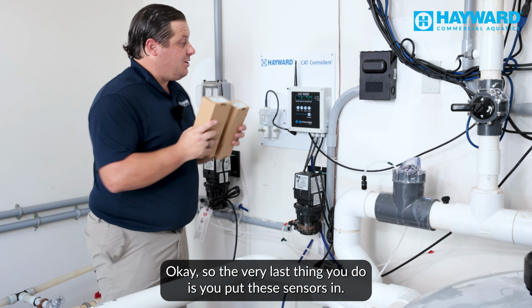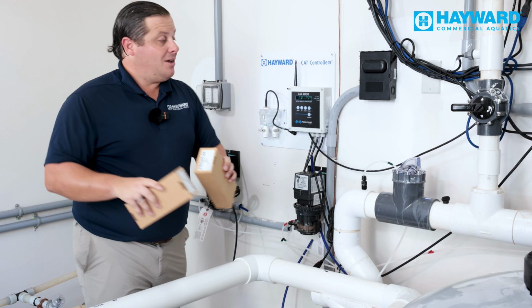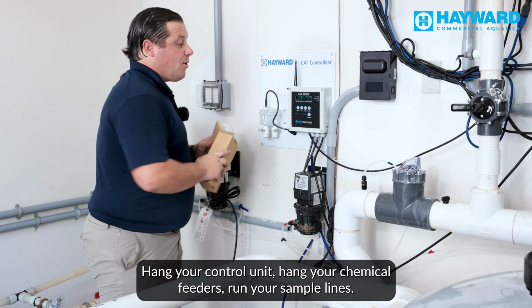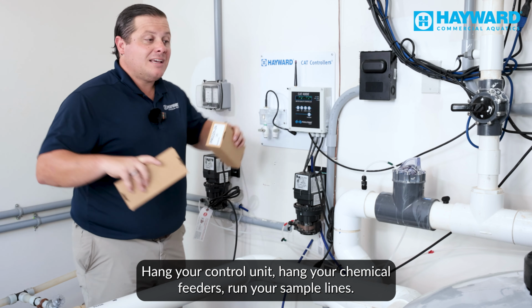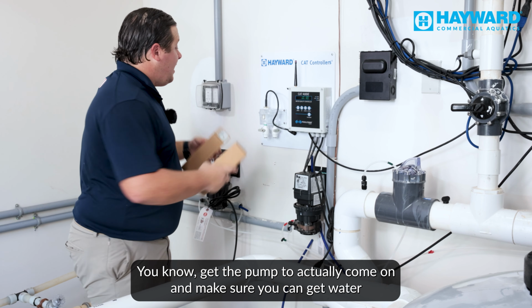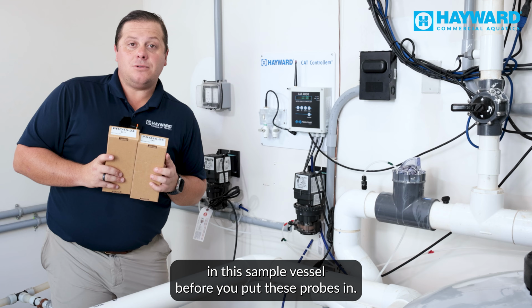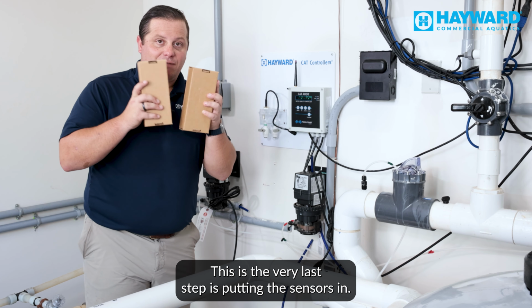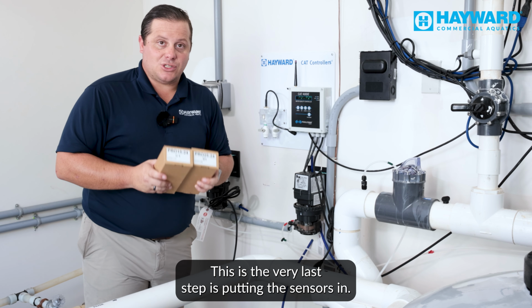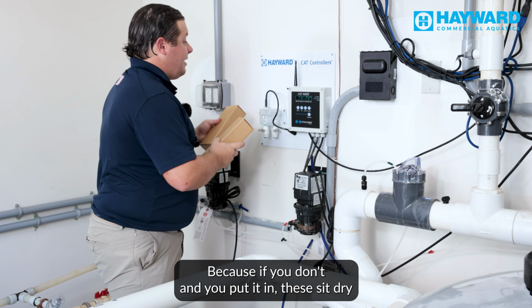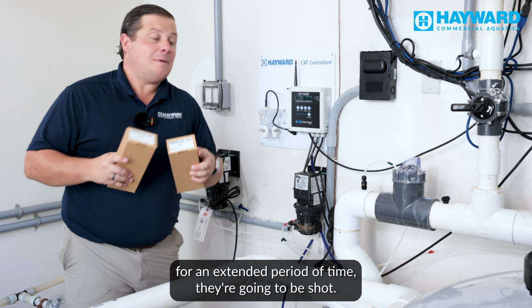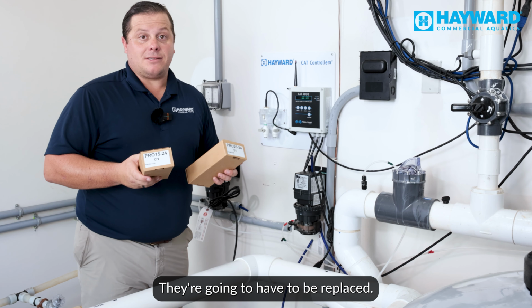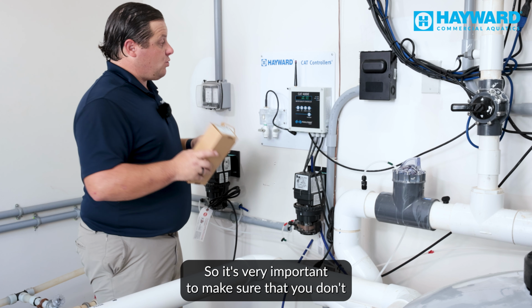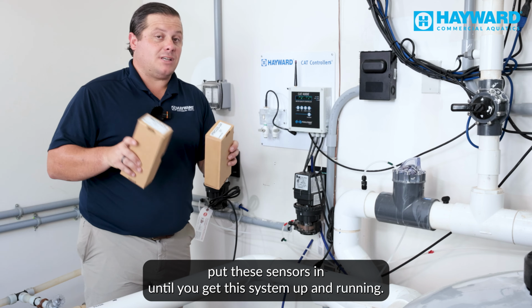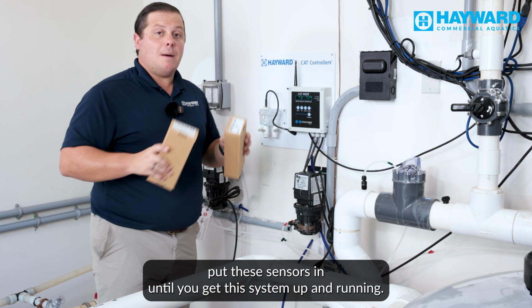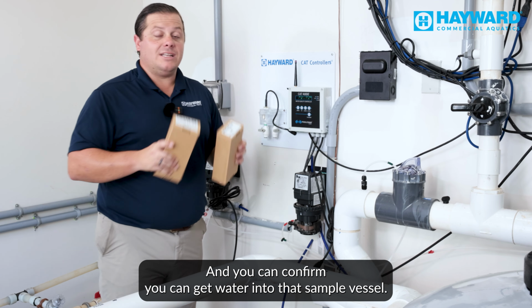Okay, so the very last thing you do is put these sensors in. All right, hang your control unit, hang your chemical feeders, run your sample lines, get the pump to actually come on, and make sure you can get water in this sample vessel before you put these probes in. This is the very last step: putting the sensors in. Because if you put them in and they sit dry for an extended period of time, they're going to be shot and have to be replaced. So it's very important that you don't put these sensors in until you get this system up and running and you can confirm you can get water into that sample vessel.